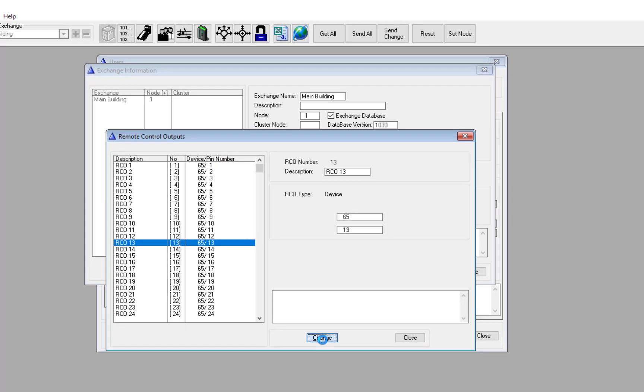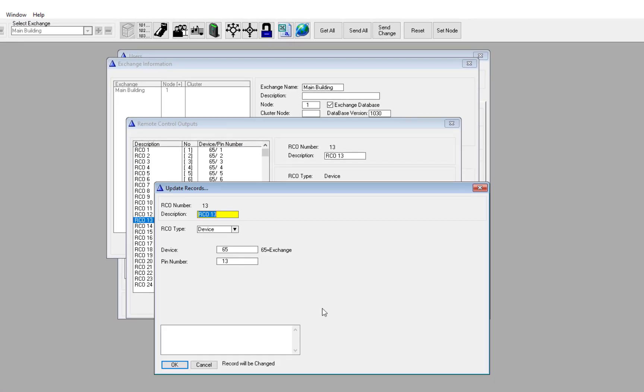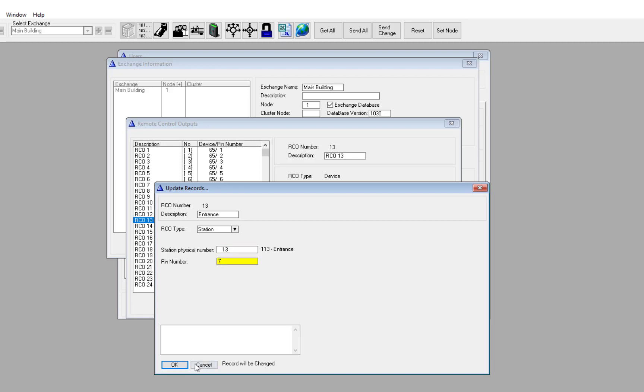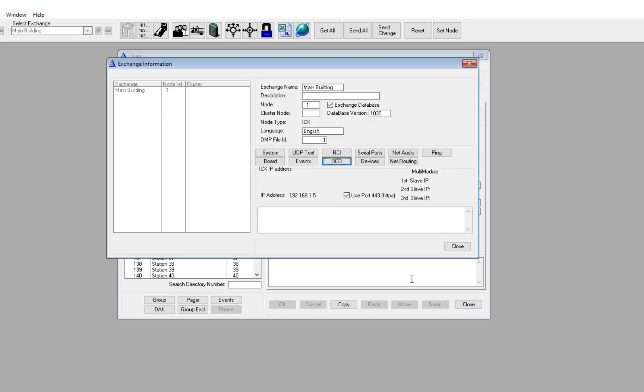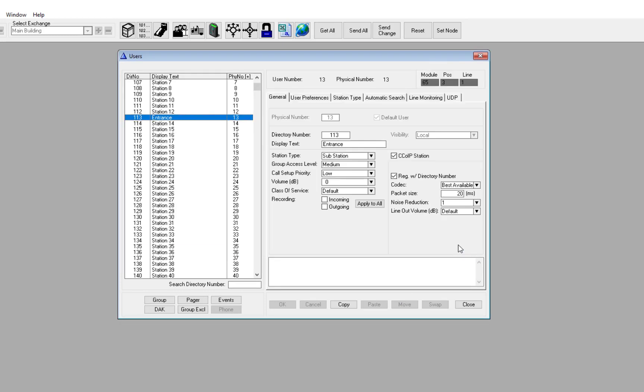Press Change. You may now enter a descriptive name for the output. Set RCO type to Station. Enter the physical number of the Entrance, which you already have made a note of. Set the pin number to 7 — this is the internal address of the relay.